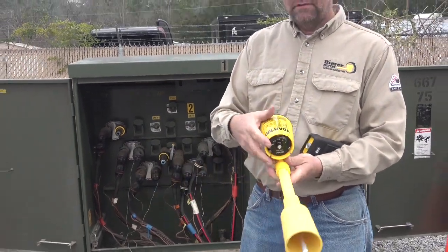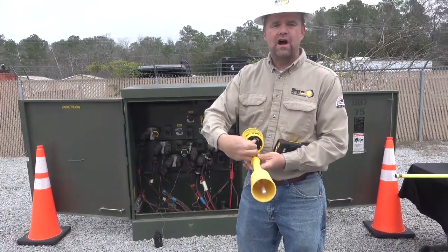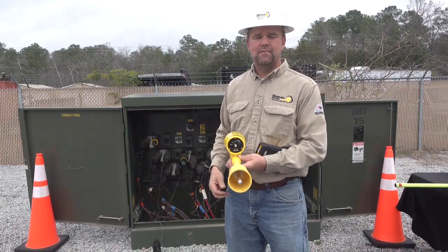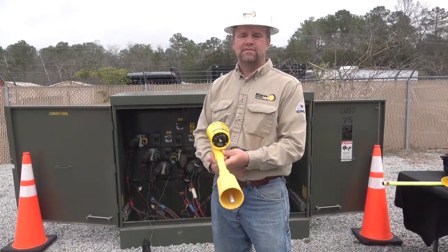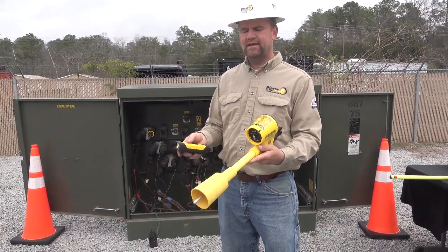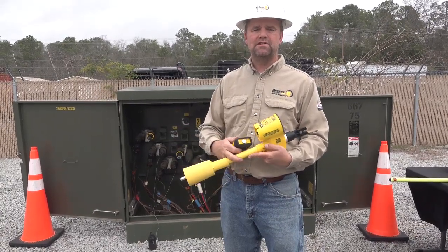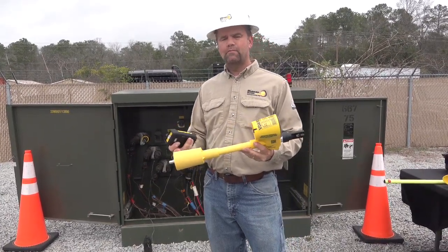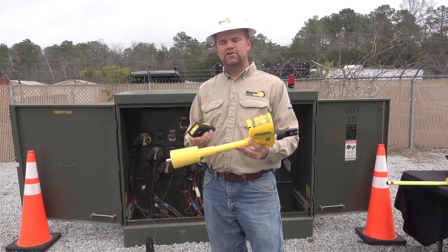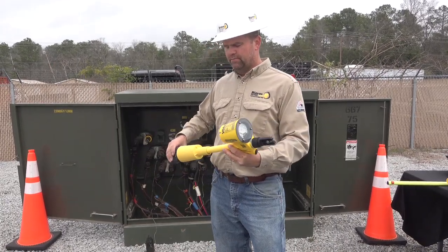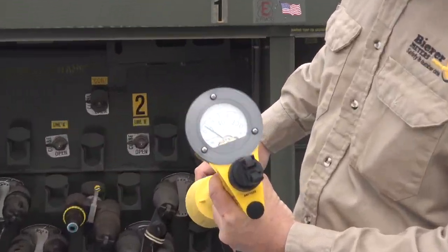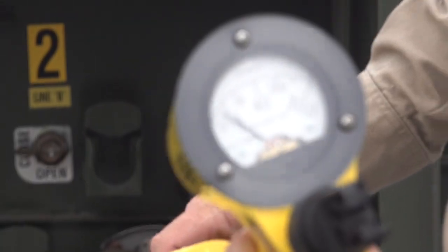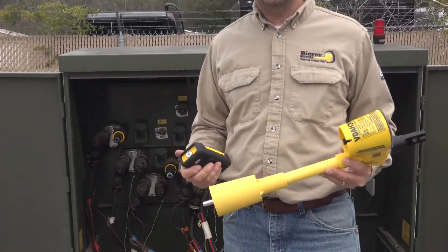Then I want to turn the device to the first on position on my selector switch. Take my handheld power supply, since this is my known voltage potential, and I'm going to test it through my bushing adapter into the tool. So I'll press it on and see a deflection near 7 kV every time I touch the end of my bushing adapter.